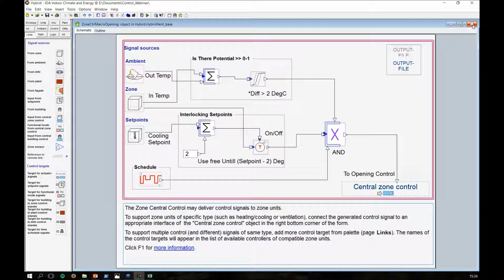Now, some might argue maybe 2 degrees is too much. We might want half a degree or 1 degree. But this deadband, this interlocking between the opening of windows, is very, very important from a control perspective, to avoid overlapping set points. And the way I'm opening here is, in one case I'm using a proportional controller, in the other I'm using a thermostat. And the thermostat basically acts as an on and off controller. It's going to give me a signal of 1 and 0. So that's how I'm opening my windows.